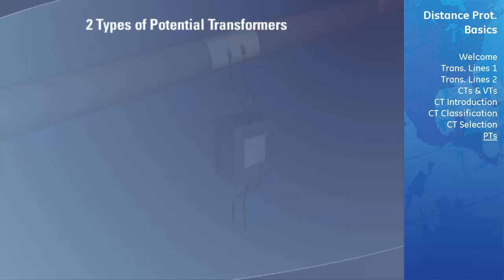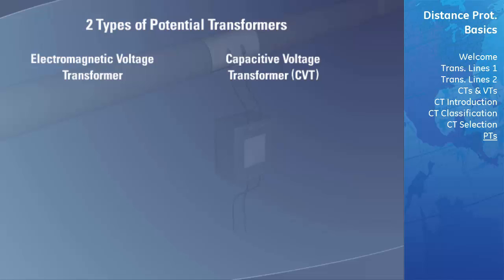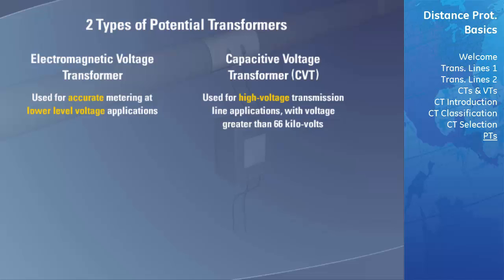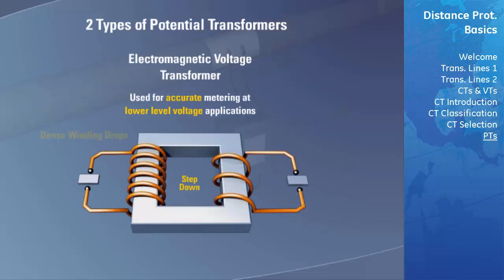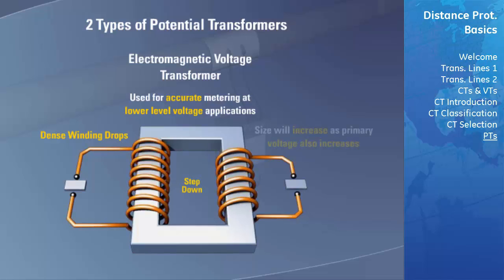There are two different types of potential transformers used today: the electromagnetic voltage transformer and the capacitive voltage transformer. Electromagnetic voltage transformers are usually used when accurate metering needs to be performed for lower voltage applications. Capacitive voltage transformers are commonly used in high voltage transmission line applications where the voltage is higher than 66 kilovolts. Electromagnetic voltage transformers have dense winding designs to accurately scale down the voltage and maintain a consistent ratio. Due to the small amount of voltage drop per winding, electromagnetic voltage transformers increase in size as the rated primary voltage increases, and their cost tends to increase at a disproportionate rate to the primary voltage rating.